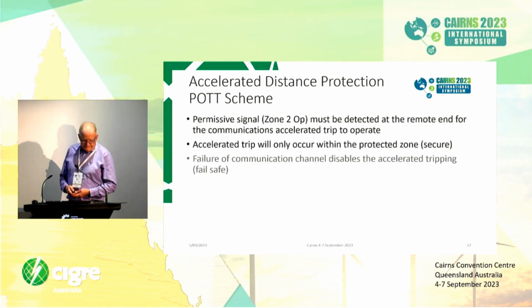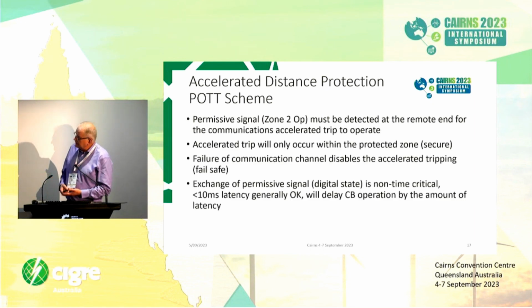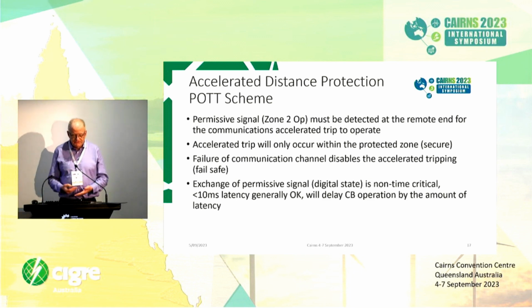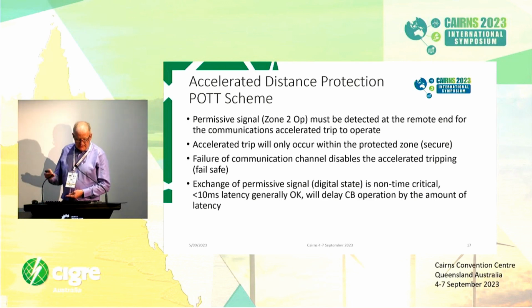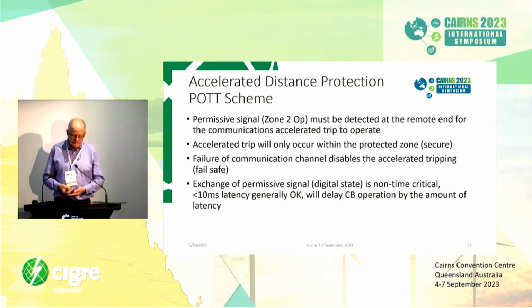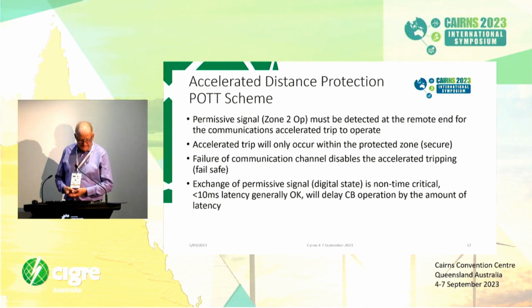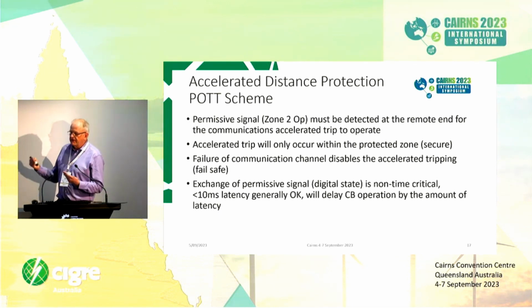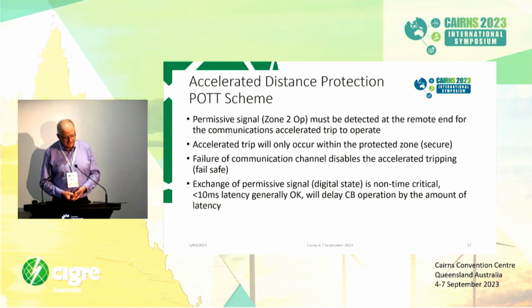So this is just a summary of what I've spoken about already. The permissive zone 2 operation must be detected at the remote end for the accelerated trip to operate. The accelerated trip will only occur for the protected transmission line you're trying to protect, so that's a secure tripping scheme. The failure of the communication channels will disable the accelerated tripping, so that's good. It's a fail-safe from a protection and communications perspective.